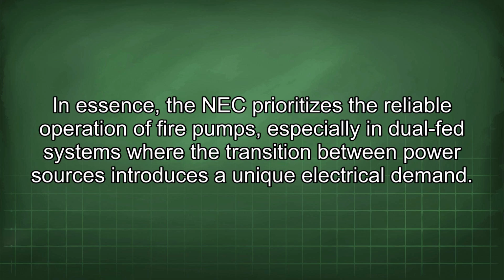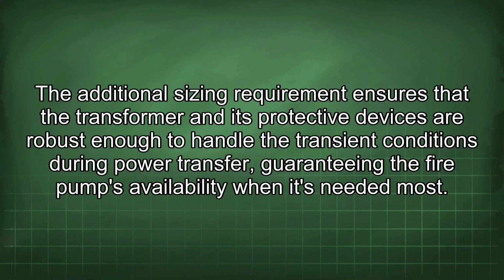In essence, the NEC prioritizes the reliable operation of fire pumps, especially in dual-fed systems where the transition between power sources introduces a unique electrical demand. The additional sizing requirement ensures that the transformer and its protective devices are robust enough to handle the transient conditions during power transfer, guaranteeing the fire pump's availability when it's needed most.